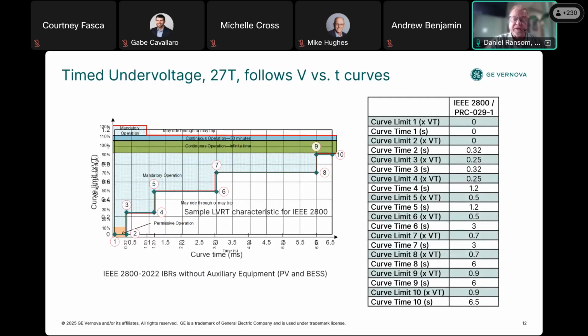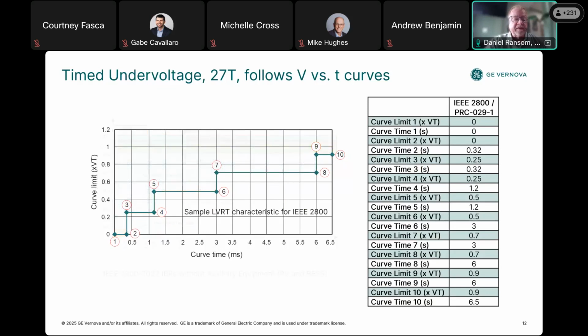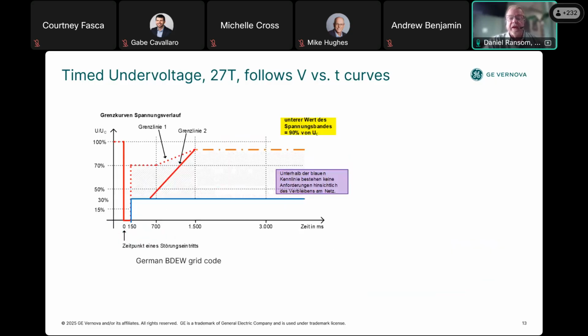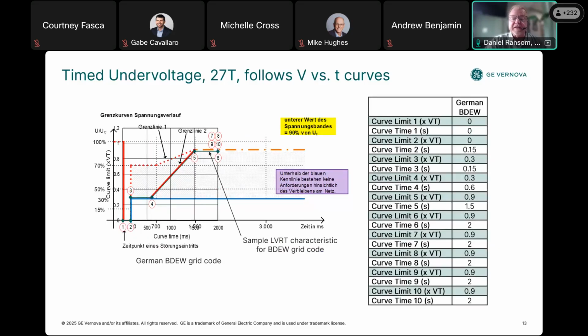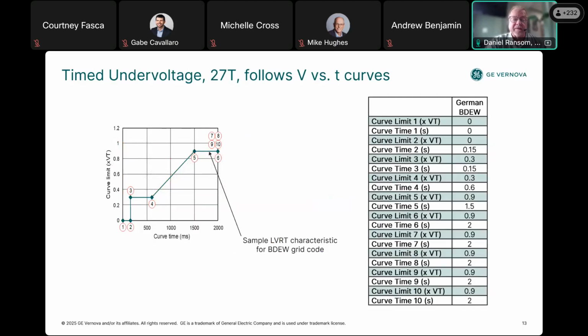The relay monitors grid support for brief voltage drops and responds for voltage drops that enter the operation region of the configurable curve as shown here. If the voltage drop exceeds the curve, the timed undervoltage element issues a notification to the plant controller. And here you see the graph alone without the standard behind it. Here's the German BDEW grid code, and here are the 27T curve coefficients for the German BDEW grid code. And here's the relay graph without the code behind it.